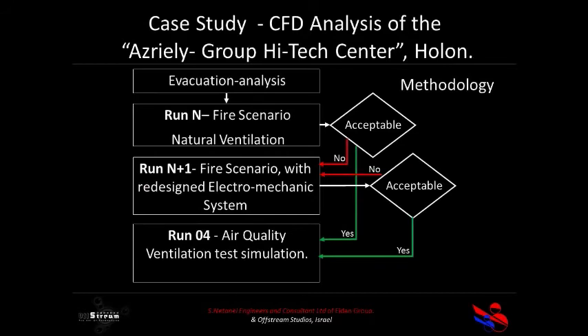One thing also about the model is all levels have a 2.5 meter ceiling height, which is a low clearance height, which you can understand means you cannot prove smoke control with tenability of smoke height level on a 2.5 meter ceiling. It just begins with not going through the code.